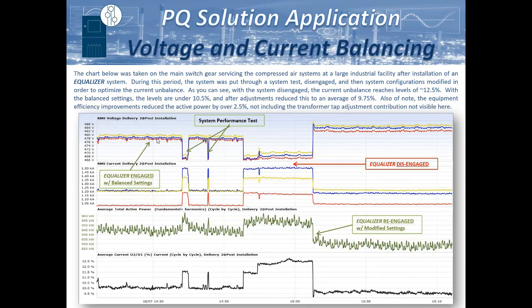So the main purpose of this facility, they were trying to maximize their energy efficiency. While I was looking at the data on his system as he was at the unit, we just did some system tests and turned the system off under its standard balance configuration. With our system, you could actually tweak the controller to perform. It's got a lot of flexibility on how you tell it to perform. It's not just an on-off kind of functionality. You can tell it to base the compensation on the average of all three legs, or on the average of only two of those three, or just based on one.